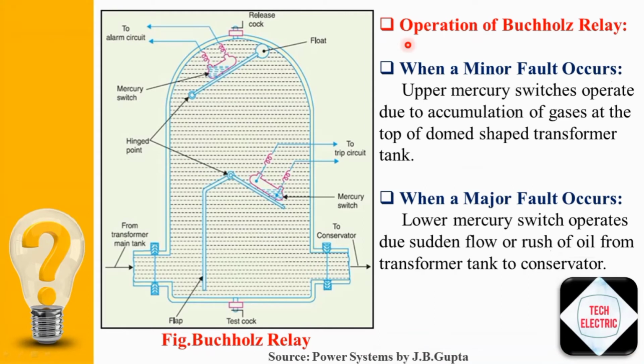Now the next topic of the session is operation of Buchholz relay. When a minor fault such as core heating or turns fault occurs in the transformer unit, heating occurs in the transformer tank. Due to this heat, the transformer oil gets evaporated. Due to this, gases start to accumulate at the top of the transformer tank. When these gases reach a particular level, the oil level in the transformer tank falls. Therefore, the mercury type switch attached to the float is tilted, so it closes the alarm circuit and rings the bell. Thereby, the operator knows that there is some incipient fault in the transformer. The transformer is disconnected at the earliest possible and the gas sample is tested.